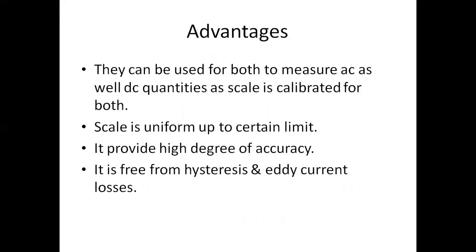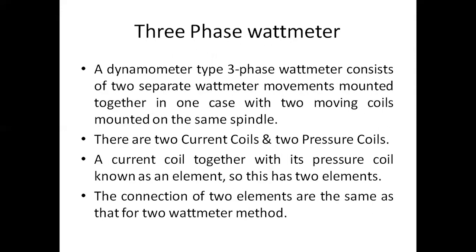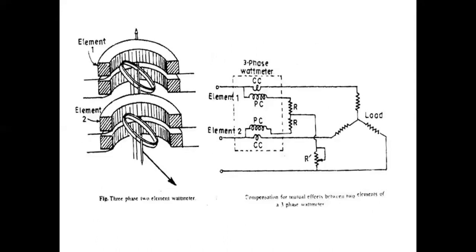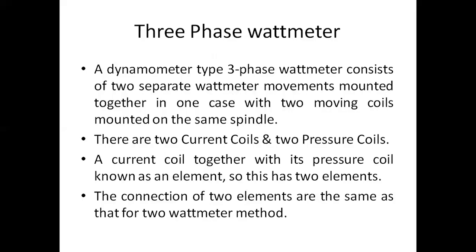Now moving to the second part — the three phase watt meter. We again have the dynamometer type watt meter. A three phase watt meter is essentially two single-phase watt meters connected together. A dynamometer type three phase watt meter consists of two separate watt meter movements mounted together in one case, with two moving coils mounted on the same spindle.